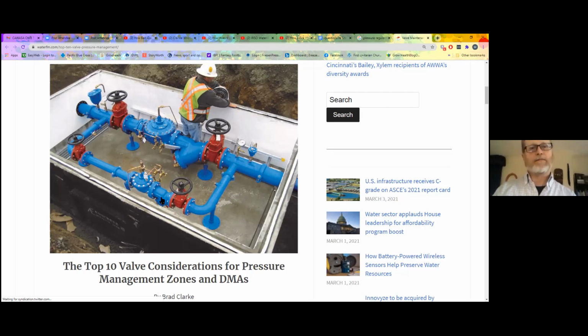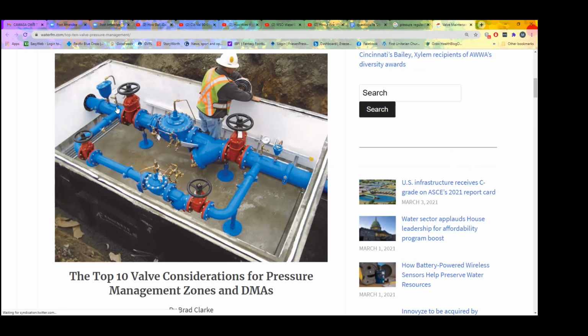So strainers in front of both, and the strainers can be blown off through the bottom or the flange removed. And it's basically a basket strainer. So you can pull the screen out and clean it if it's got dirty water. The operator here is going to put a gasket down, and it's a two-piece pre-constructed box. Everything arrives in the lower half of the box, lower it down, tie it in, pour thrust blocks, and Bob's your uncle.